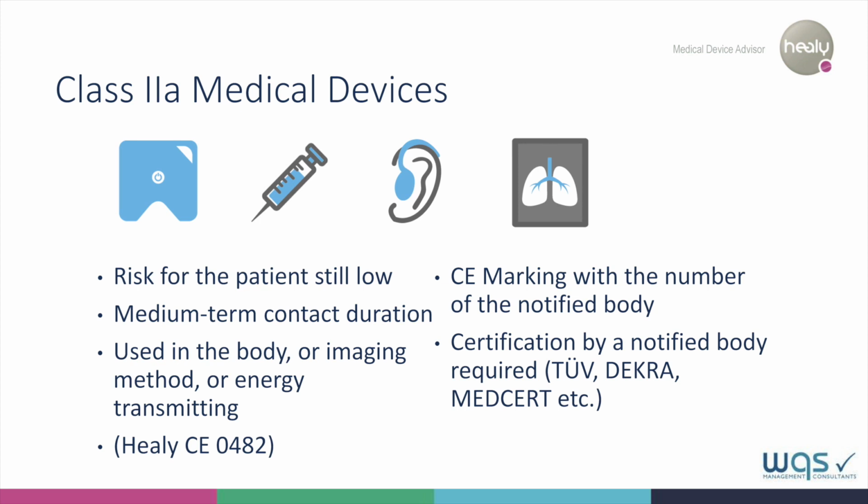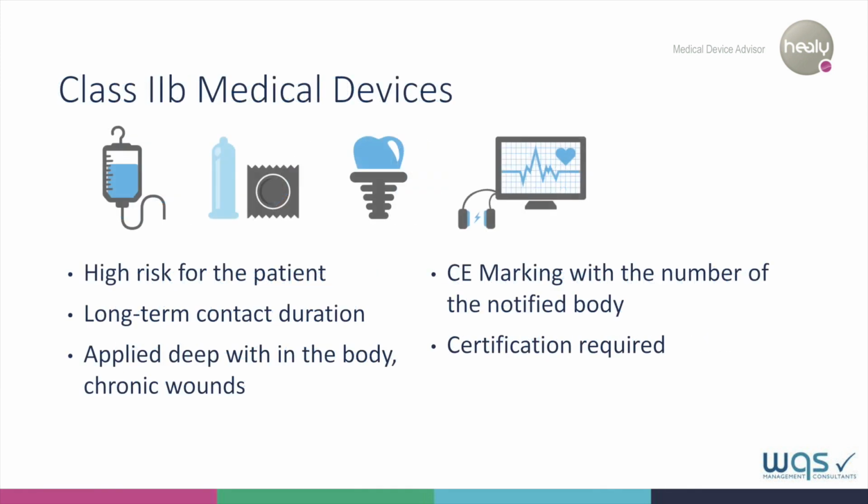The duration of its application can be determined as medium term, and the application of microcurrent for therapy is transferring energy to the user's body. All products in this class bear the CE mark of a notified body such as MedCert, which means that the manufacturer in the sense of the directive is certified. Class 2B products differ from the previous ones in terms of risk, duration of use, and depth of treatment. An example of this class is the administration of infusions. Certification and CE mark correspond to Class 2A.